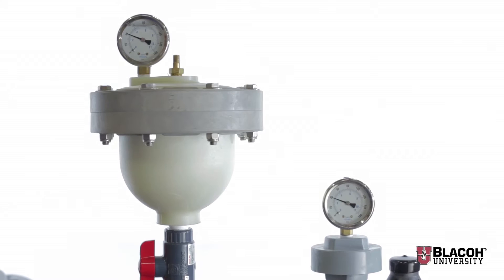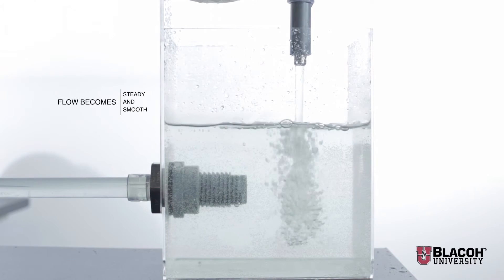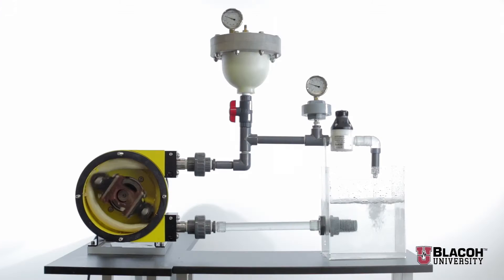As we activate the dampener by opening an isolation valve, you will notice that instantly the flow becomes steady and smooth, centrifugal-like, and that the needle on the pressure gauge is nearly stabilized, indicating that there are no more pressure swings, thus protecting piping and other system components.